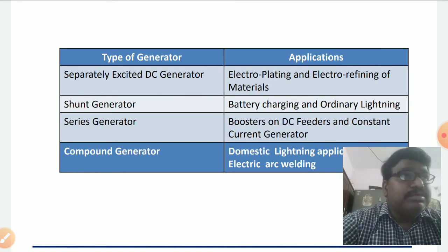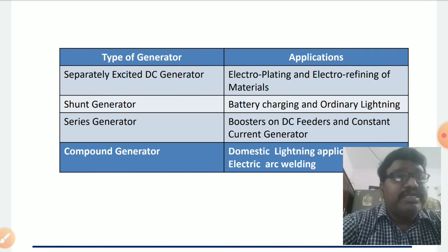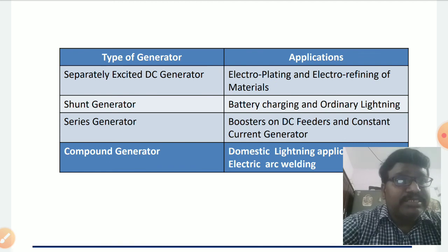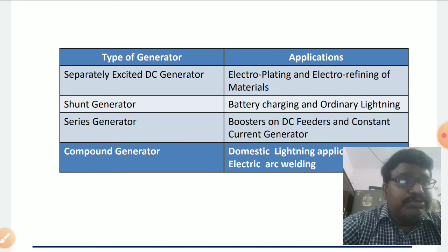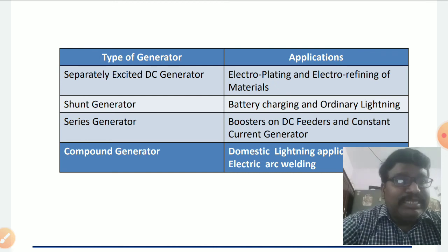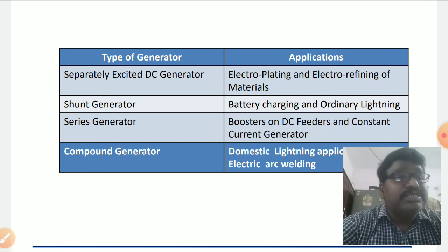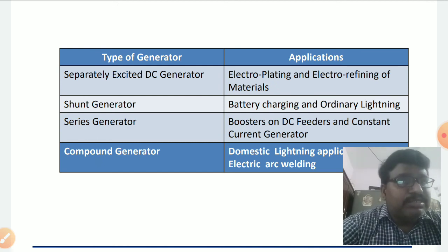Because of its characteristics, the series generator is majorly used as a booster for DC feeders. At very heavy loading conditions, there is a huge voltage drop in transmission or distribution lines, so the series generator is used to boost up the voltage in distribution lines. It is also used as a constant current generator, since it supplies constant current to the load.